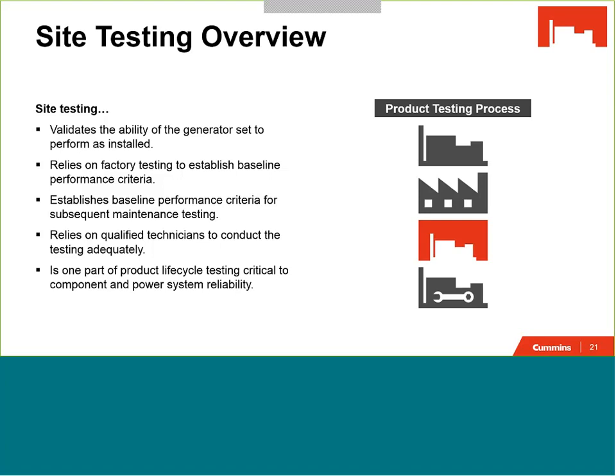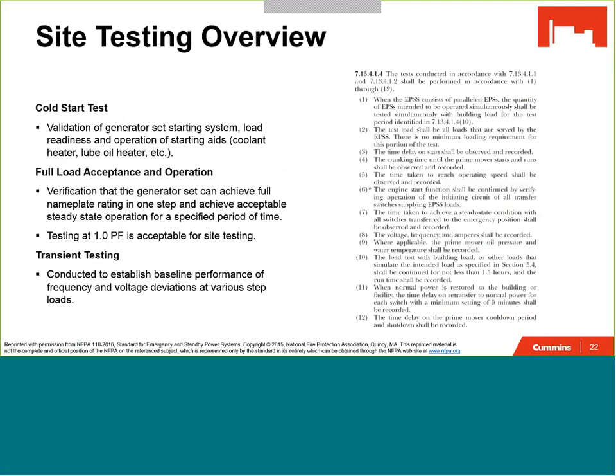installed. On one hand, it's a test of the generator set, but it's also a test of its integration with the facility, so it's testing much more than just the generator set. Site testing relies on factory testing having been conducted in order to look back at a set of baseline performance criteria. This is also establishing a similar baseline performance criteria for subsequent maintenance testing that will be conducted later on down the line. Site testing relies on qualified technicians to conduct the testing adequately. And of course, I'll repeat it again, site testing is just one of the four pieces of the product testing life cycle. So let's look at a couple different recommendations or guidelines for site testing.